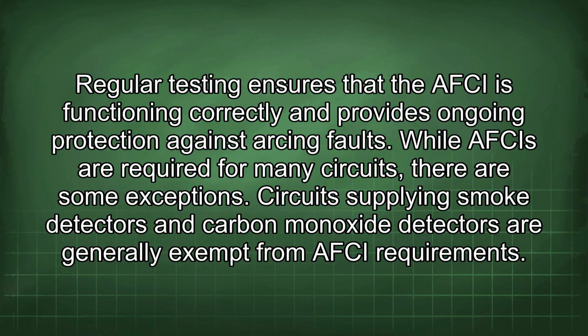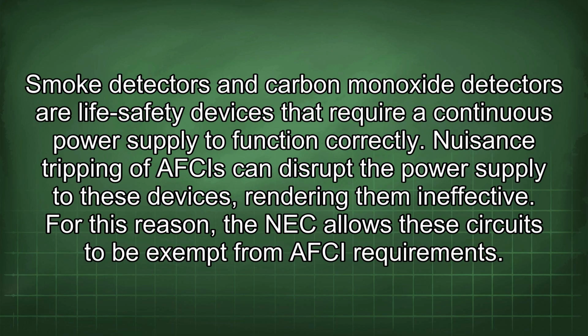While AFCIs are required for many circuits, there are some exceptions. Circuits supplying smoke detectors and carbon monoxide detectors are generally exempt from AFCI requirements. Smoke detectors and carbon monoxide detectors are life safety devices that require a continuous power supply to function correctly. Nuisance tripping of AFCIs can disrupt the power supply to these devices, rendering them ineffective. For this reason, the NEC allows these circuits to be exempt from AFCI requirements.